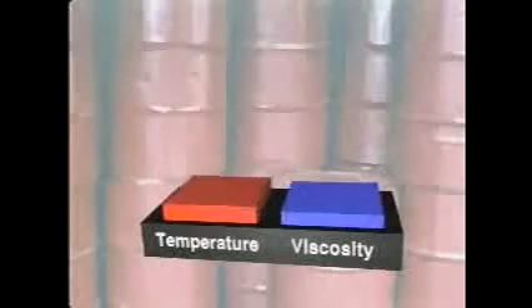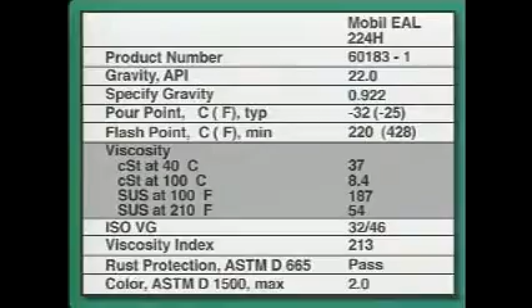If a lubricant is used where large changes in temperature occur, the lubricant's viscosity index is important. The viscosity index is a measure of the lubricant's viscosity change in relation to temperature change. If, when temperature changes a large amount, the lubricant's viscosity changes a small amount, the lubricant has a high viscosity index, or VI. If, when temperature changes a relatively small amount, the lubricant's viscosity changes a large amount, the lubricant has a low VI. Consequently, the temperature at which the viscosity measurement was obtained must be stated.